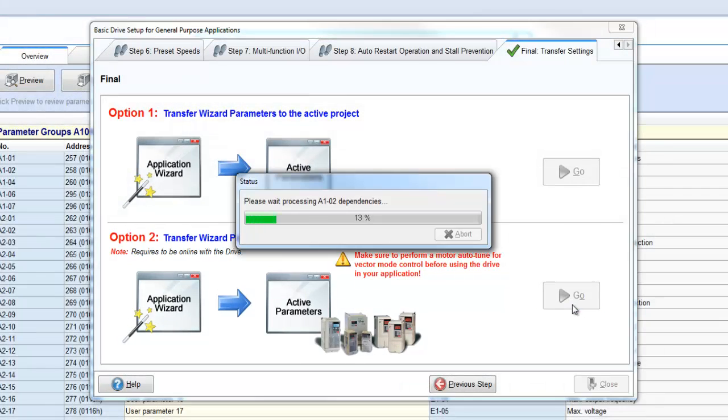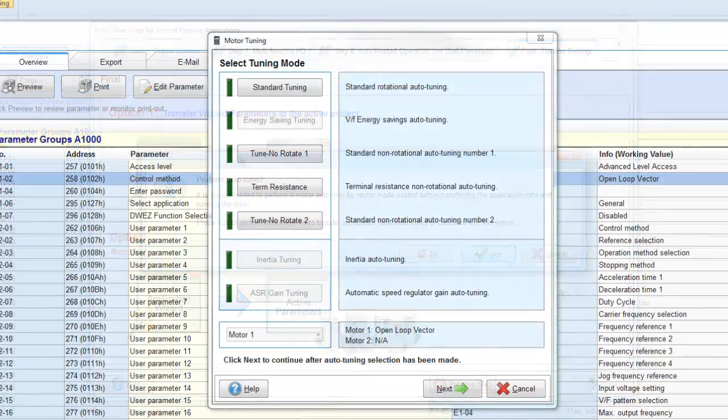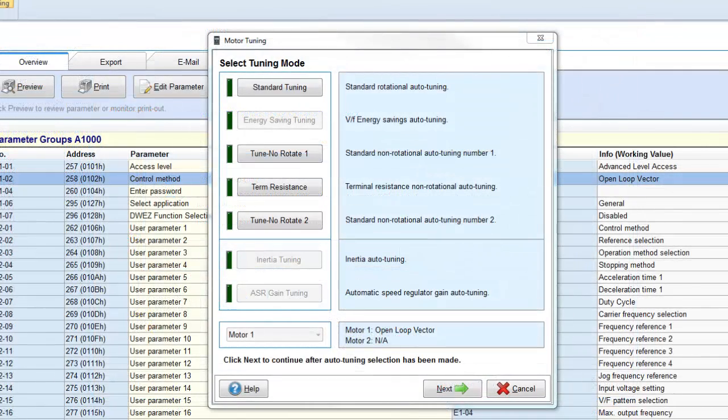At this point, the Wizard will prompt you to perform an auto-tune. Auto-tuning is only an option and is not required. However, it is highly recommended in order to achieve the most torque per amp from the motor.